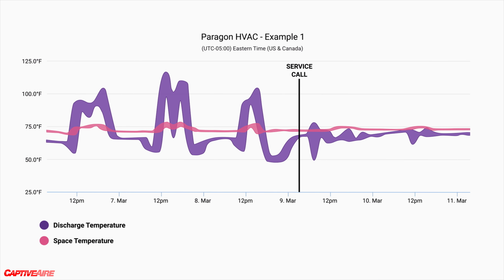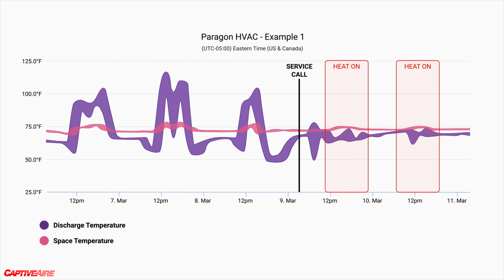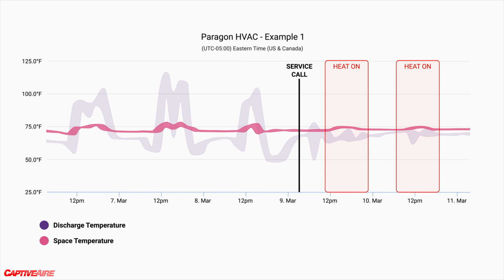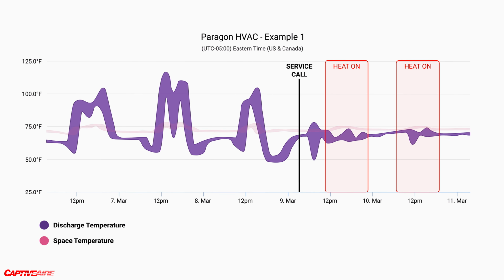And once that was done, every time they called for heat again, you can see the pink line was those space temperatures creeping up and the purple was the discharge temps. After that point, every time we got a heat call, it was heating it to a much more moderate level and it was keeping a much more consistent space temperature as you expect.